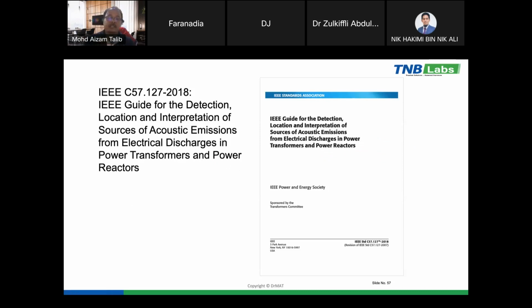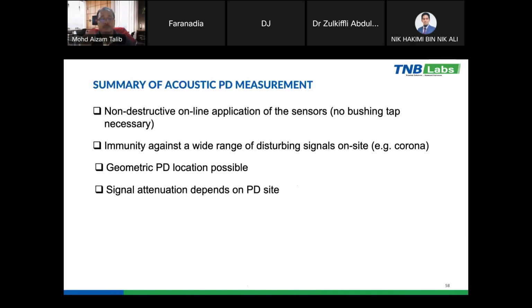So we can see the guideline on the acoustic emissions for PD in the power transformer based on IEC 60270 and IEEE C57.127. And then an example summary of the acoustic PD measurement. It is a non-destructive online application. It has immunity against a wide range of disturbing signals on site, because the transformer tank itself acts as a shield. So signals from outside the transformer do not disturb the electromagnetic signal in the transformer. And through this acoustic measurement, we are able to locate the PD activities. But the signal attenuation depends on the PD source.